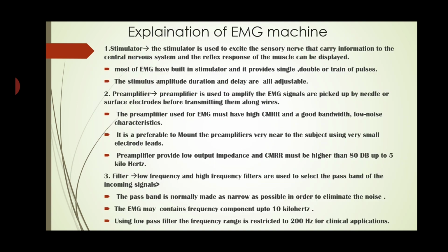The stimulator is used to excite the sensory nerve that carries information to the central nervous system, and the reflex response of the muscle can be displayed. Most EMG machines have a built-in stimulator and it provides single, double or train of pulses. The stimulus amplitude, duration and delay are all adjustable.